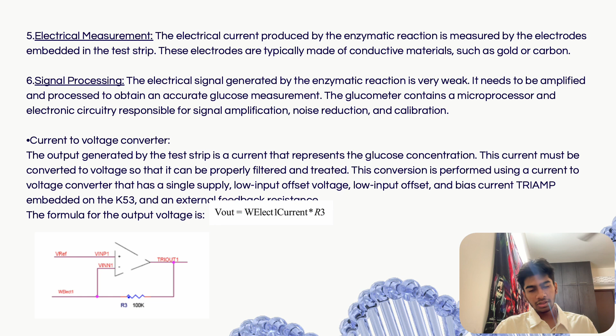Before amplification, we need to first convert the current to voltage. The output generated by the test strip is a current that represents the glucose concentration. This current must be converted to voltage so that it can be properly filtered and treated. This conversion is performed using a current to voltage converter that has a single supply, a low input offset voltage, and low input bias current. The formula for the output voltage is Vout equals the input current from the sensor itself multiplied by the resistance.